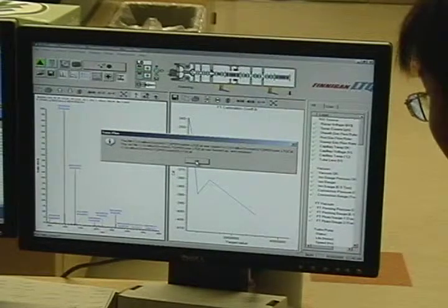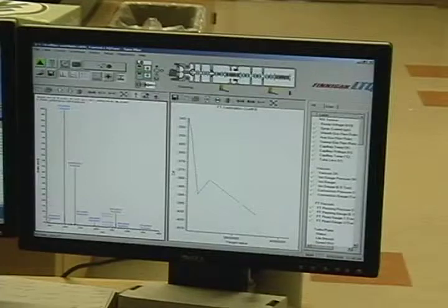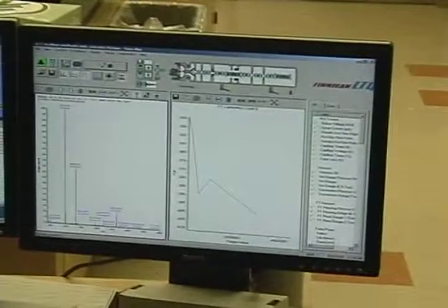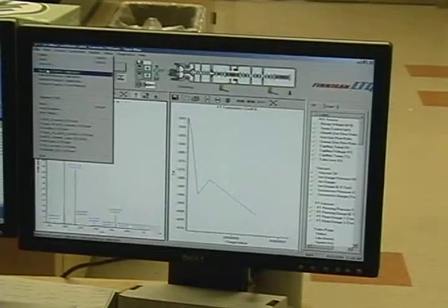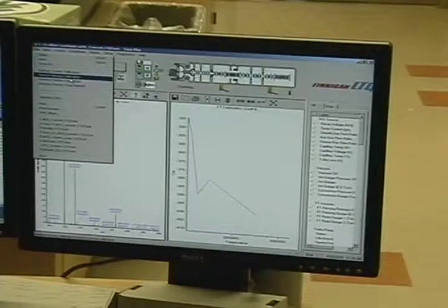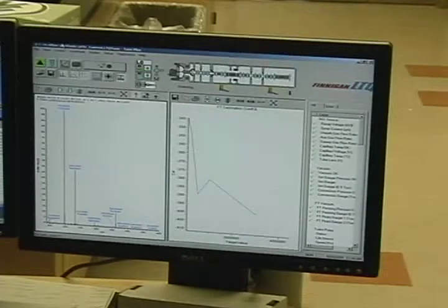Cool. Now, be very careful. What I don't like is the fact that they put backup current calibration under restore backup calibration. It's very easy to slip the finger and kill the calibration.